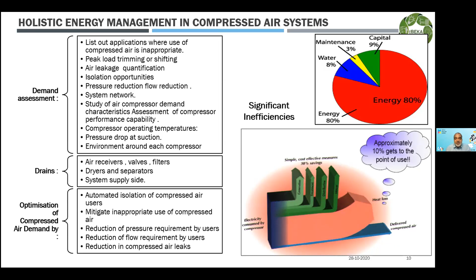And further, if demand assessment is not done, high pressure and low pressure headers are not separated, the receivers are not installed at the demand side, if there are leakages happening in the network, if we are not isolating the equipment that is not in production, then the compressor system is going to create a very high energy cost implication as far as the overall system cost is concerned. And that's why we are required to look, in totality, at how I will maintain my compressor system.